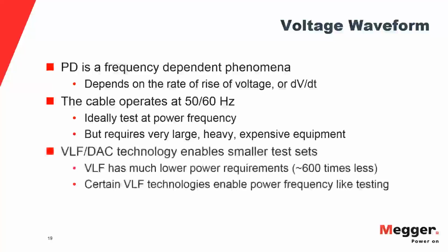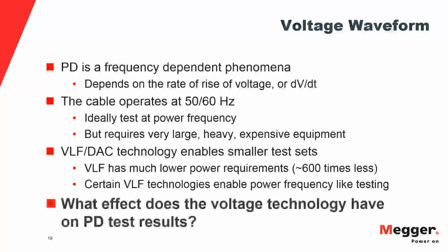Because we bring our own equipment, we can design it as PD-free as possible, so we tend to have a lower background noise as well to enable more sensitive PD testing. So that's the brief introduction. I'll talk about the voltage waveforms that we have available to us.